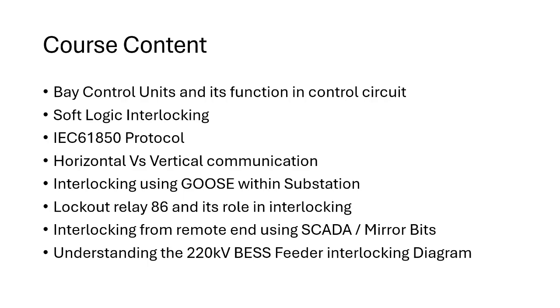Next we will learn about the lockout relay, which has ANSI code 86, and we will see its role in the substation. Nowadays lockout relays can be hardware based or software based, created through soft logic, sometimes as a built-in function inside the relay.